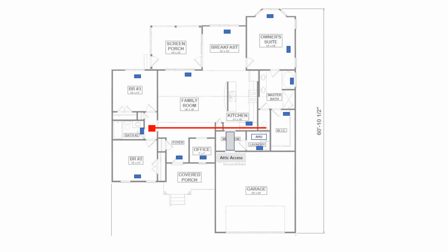This would add a significant amount of duct length, thus friction and static pressure to the system that I was going to have to design around. Fortunately, I found out about this before I had finalized my duct design. And there really wasn't any point to have jumper ducts in the smaller bedroom, because my return was going to be right there just outside of those bedrooms anyway.